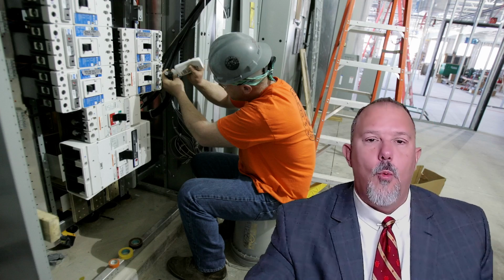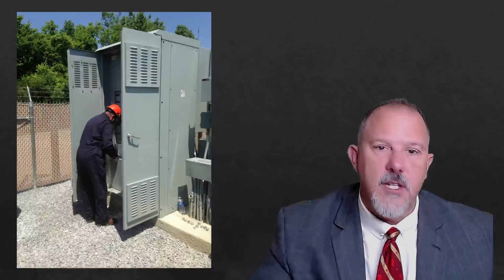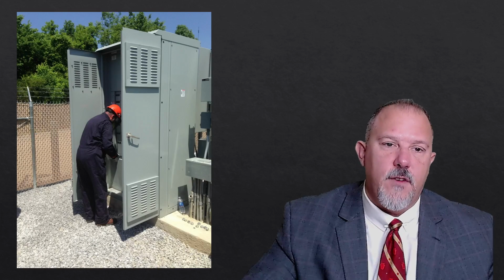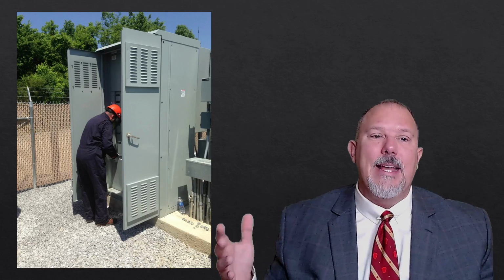When the electrical worker is going to put themselves in harm's way, you want to provide space in front of the equipment. You want that ability to get out of that room. You want the egress capabilities. You don't want this type of situation where the electrical worker, if they don't decide to clean up your garbage, tries to get this work done in this tight space. There's a lot of issues going on in these types of images.